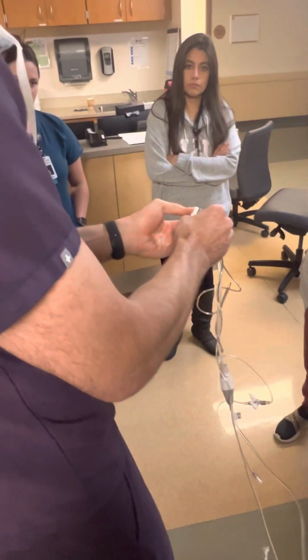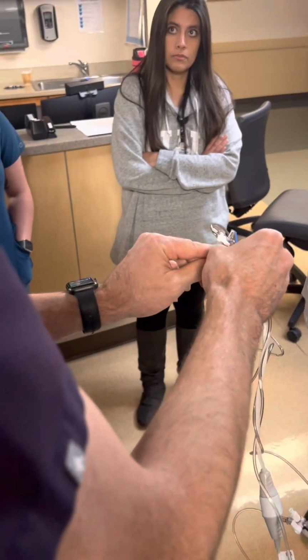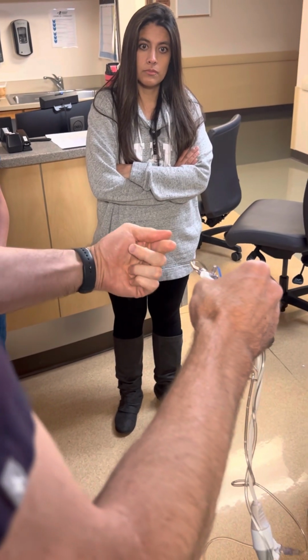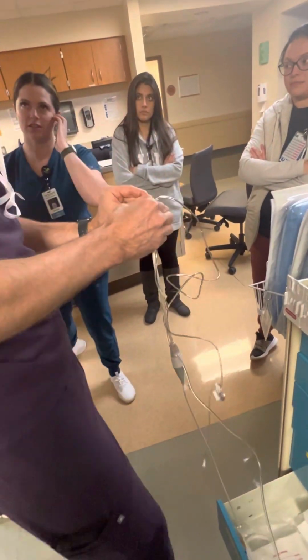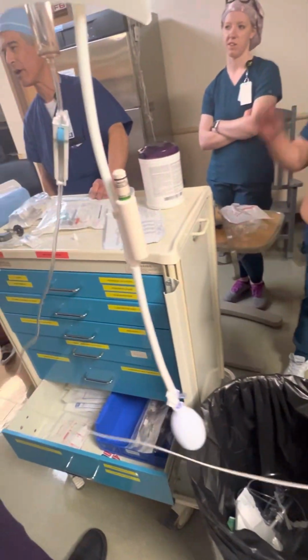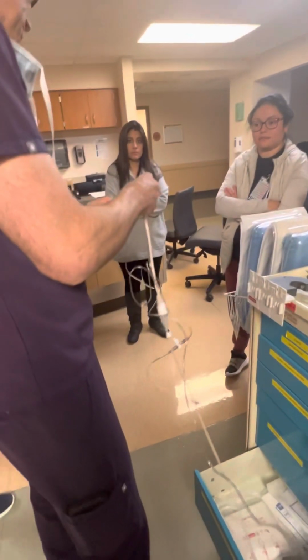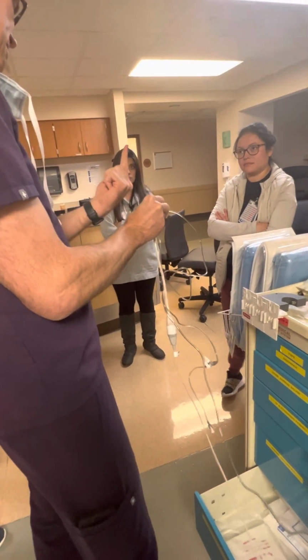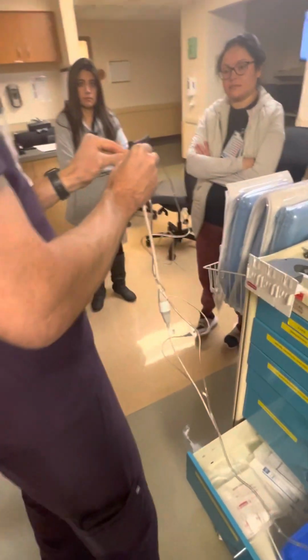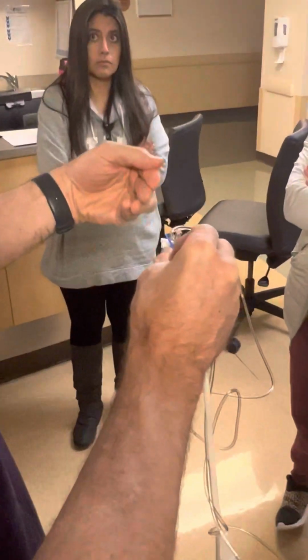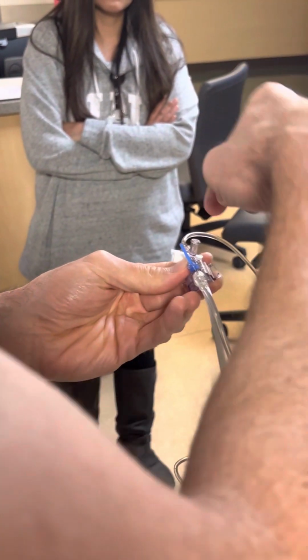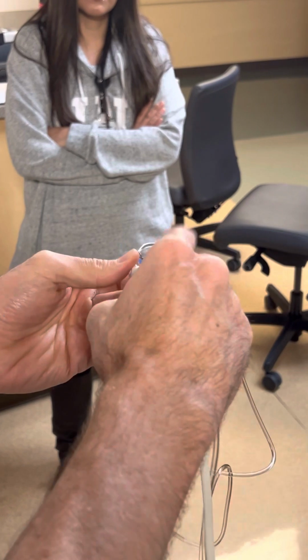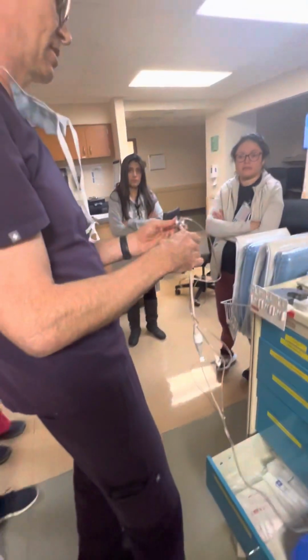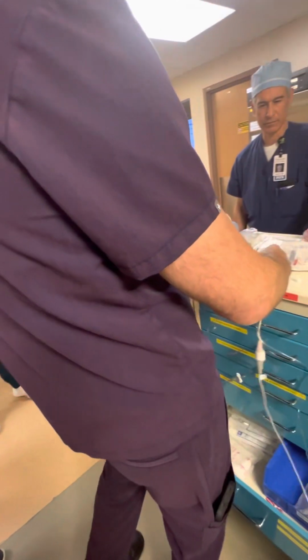So this cuts your air out and shuts the transducer off, but then opens it up so that the arterial pressure pushes blood back out at you. Will you change that one if you don't want blood shooting out when you want to zero it? So it points to off, correct? Yeah, this is off that direction. So for the patient on that side, you shut the pressure of the patient off. The air pressure can then go into the transducer, so it measures the air pressure. So this is the position you want when you zero.